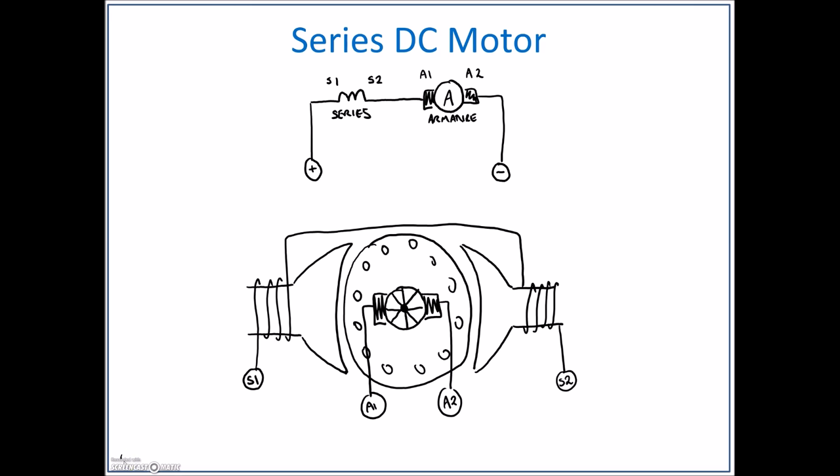Now let's see how this is going to hook up to our DC source. I put the positive on the left-hand side, so we'll put our positive here. We'll put a negative over here. It looks like I'm going from positive to S1, so I'm going to bring a lead over to S1. Then I've got S2 going to A1. S2 is going to go to A1, and then A2 is going to go back to the negative of the source.